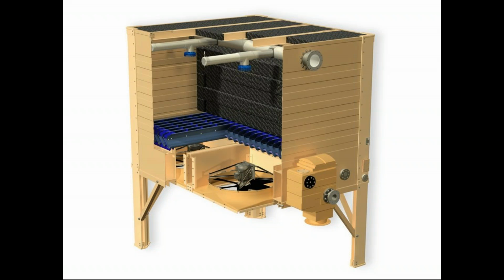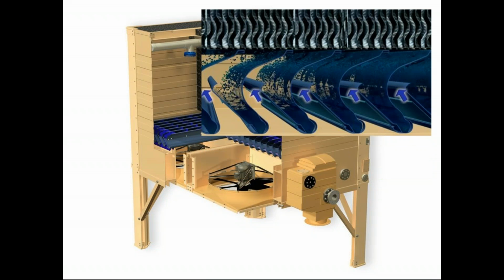What's different, obviously, is our fans are on the bottom, and you see it's a fan array on the bottom. So we have a bunch of fans on the bottom, blowing air up, going up through the top. The other thing that's unique is you have no exposed water to sunlight on this cooling tower. If I don't have water and sunlight, that means we don't have algae. If you look at a traditional cooling tower, when you walk up to it on the roof, first of all, you feel the droplets on the side of you as you're walking next to it. And the other thing is you see algae all throughout the fill of the cooling tower on a traditional tower system.